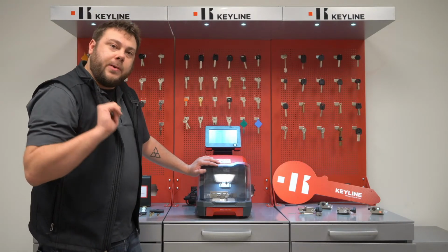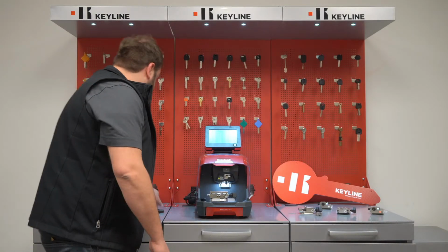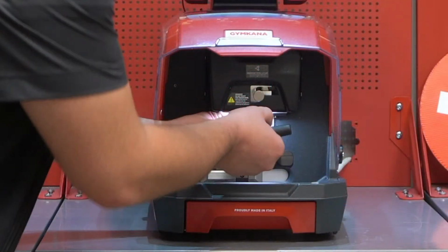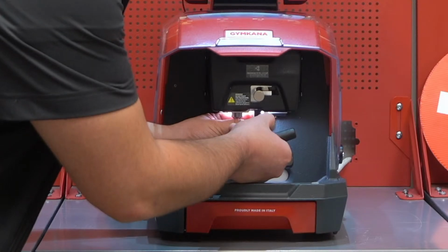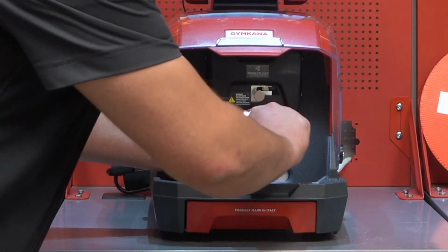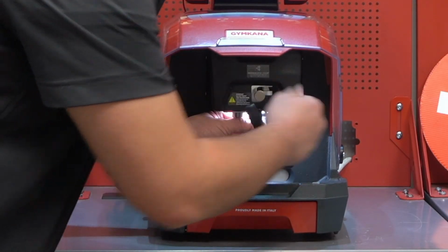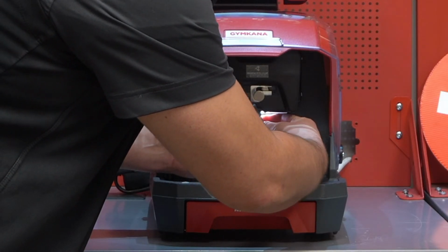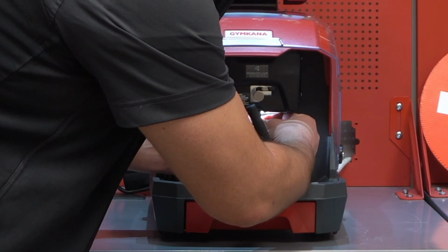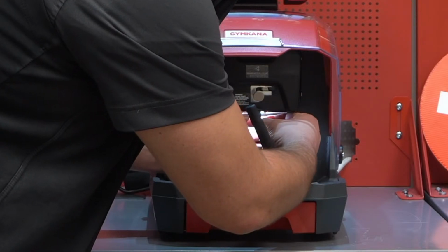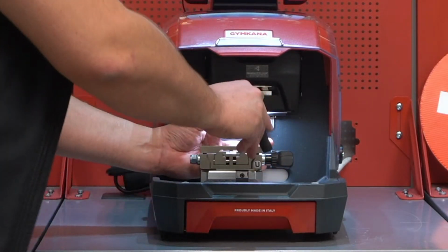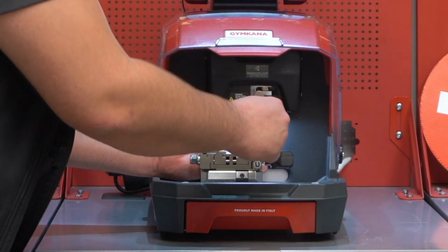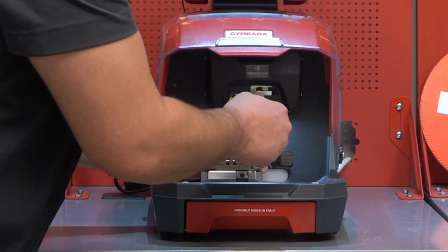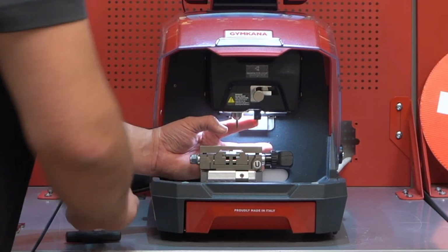First thing that we always do when we calibrate is we take out the tracer and verify that it's completely straight. How you take out the tracer is you loosen the set screw on the right hand side, and the tracer will just come right out. I'm not going to pull it out just to be safe, but you just need to make sure that it's completely 100% straight. Make sure that it's a T008, and then push it up as far as it can go.